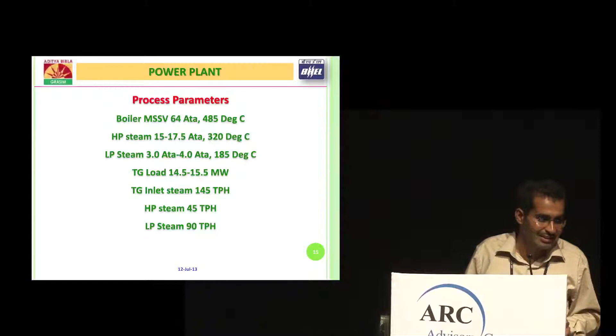And one more intricacy in the plant is that there is a pulp and fiber manufacturing concern. The pulp plant operates at a lower pressure cycle, 45 kgs, and we operate at a higher pressure cycle. So whatever is the steam shortfall in the pulp concern has to be met by our concern. And if there is any steam surplus in the pulp plant, we have to consume it by means of PRDS. So when we give it by PRDS, the turbine governor has to control the HP steam. So it is a very critical process. If the governor has some delay or is unable to control, it could cause a tripping in the turbine. So that's why the tuning of the governor is very important.